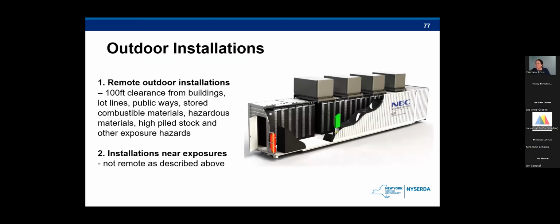So now moving on to outdoor installations. Outdoor installations are really defined as either being remote or near exposures. A system's considered remote by the code if it's at least 100 feet clearance from buildings, lot lines, public ways, stored combustible materials, and really anything else that might be hazardous. And installations near exposures is literally defined as not remote, as we described above. So basically anything within 100 feet of buildings, lot lines, or public ways is considered near exposure.